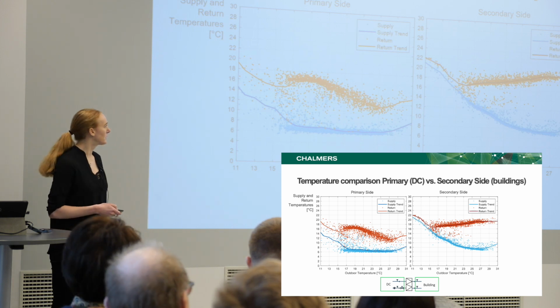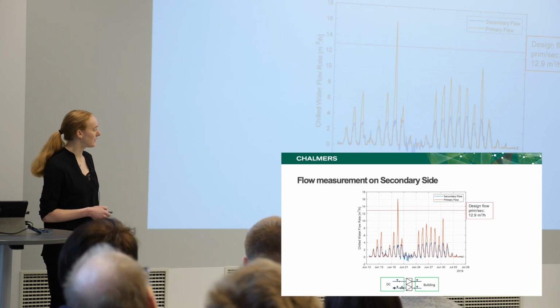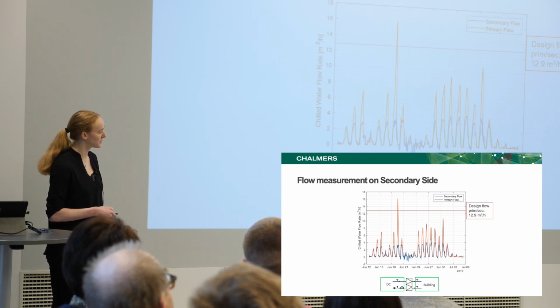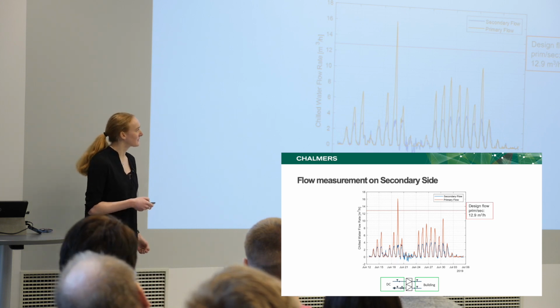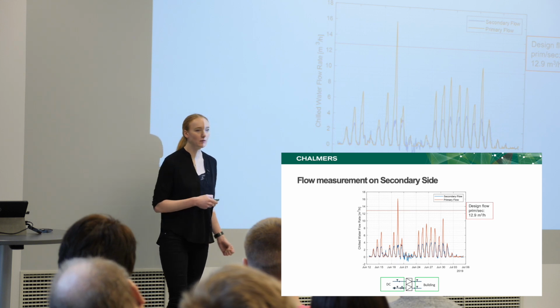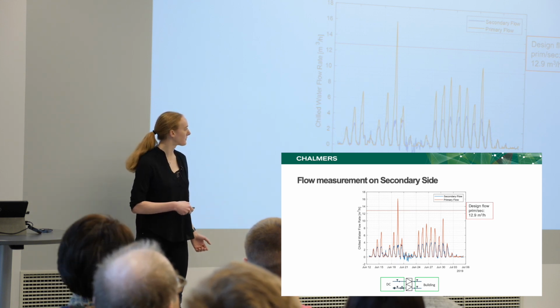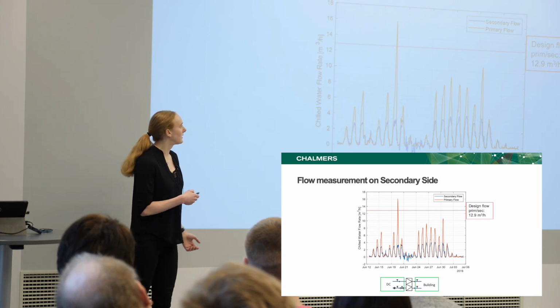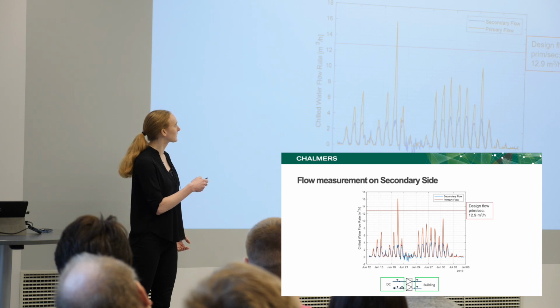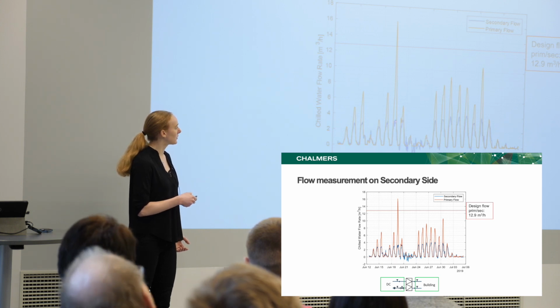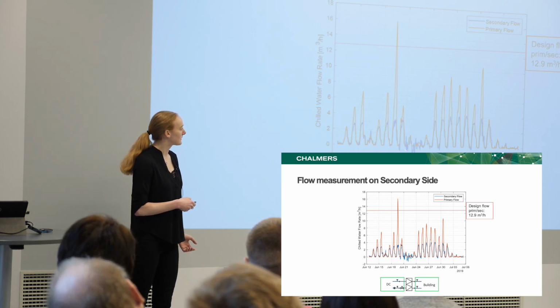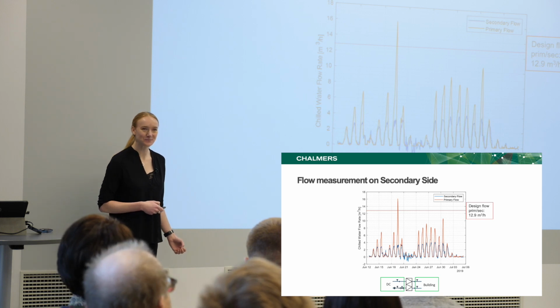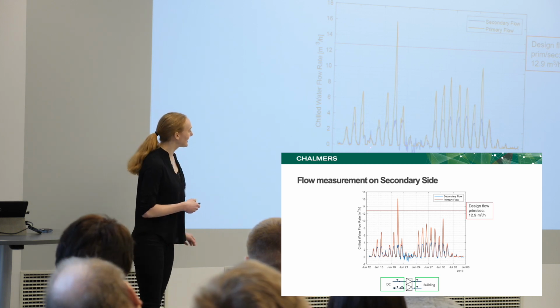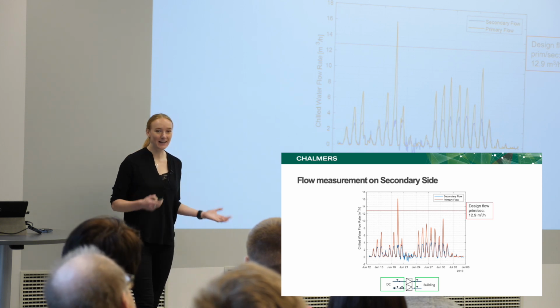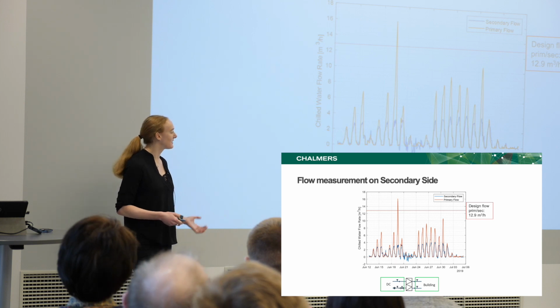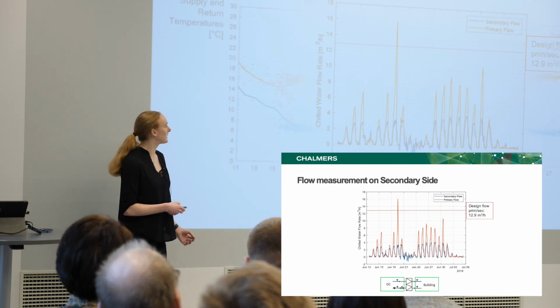So this is when we decided to measure the flow on both sides. This side we measured last summer. And the fact is that the heat exchanger, or most heat exchangers, are designed to have the same flow on both sides. But what we saw in this substation is that the primary flow, which are these orange peaks, go up to here, compared to what the secondary flow is, this blue line. It's not negative flow here, it's just that the measurement equipment couldn't detect the low flow. But anyway, it's a large imbalance between the two sides of the heat exchanger. And this is what caused the return temperature to drop here.